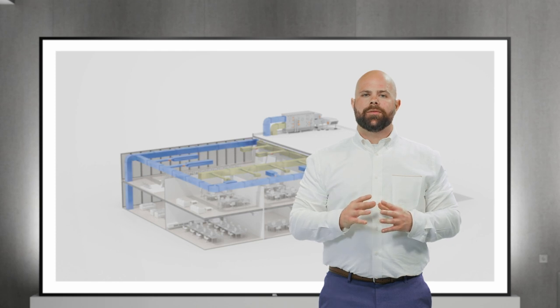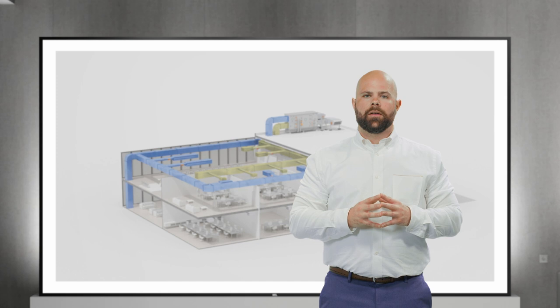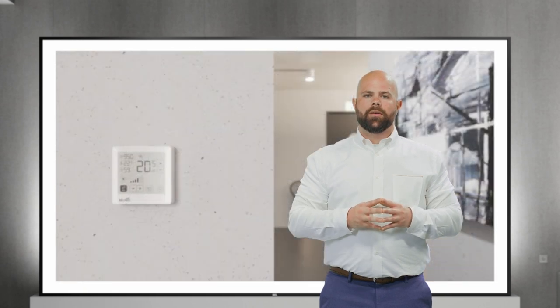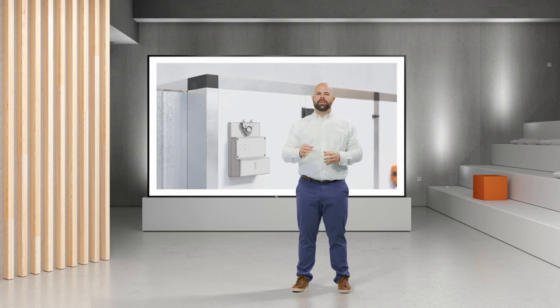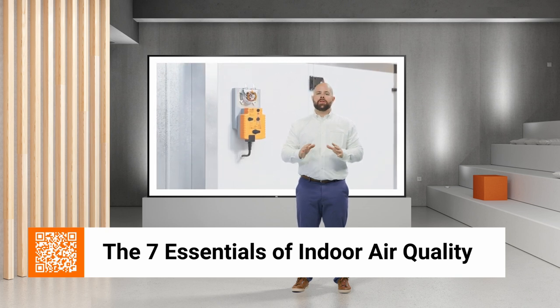In some applications, a central ventilation unit provides fresh, clean air to multiple zones, and each of those zones has its own unique requirements for the amount of fresh air. A way to optimize this is to use a demand control ventilation tactic. In this operation, we provide just the amount of outside air needed to offset the CO2 gases. All you need is a CO2 sensor and a little bit of smarts. This is the best way to optimize for indoor air quality and also save energy. With continuous reliable measurement and ensuring the proper flow gets into the space, you've already completed two of the seven essential steps towards healthy indoor air.